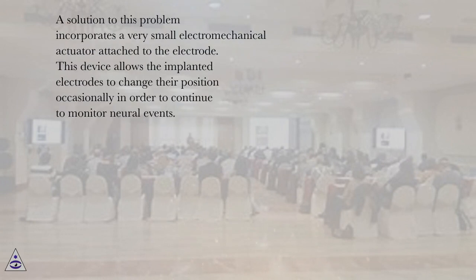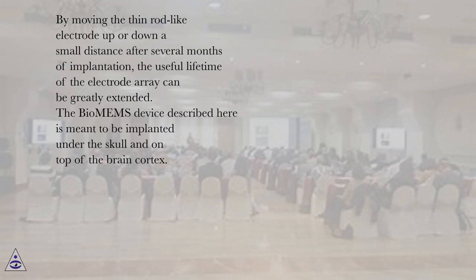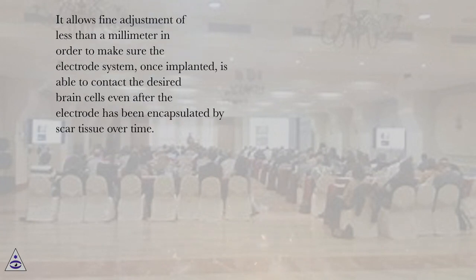A solution to this problem incorporates a very small electromechanical actuator attached to the electrode. This device allows the implanted electrodes to change their position occasionally in order to continue to monitor neural events. By moving the thin rod-like electrode up or down a small distance after several months of implantation, the useful lifetime of the electrode array can be greatly extended. The BioMEMS device described here is meant to be implanted under the skull and on top of the brain cortex. It allows fine adjustment of less than a millimeter in order to make sure the electrode system, once implanted, is able to contact the desired brain cells even after the electrode has been encapsulated by scar tissue over time.